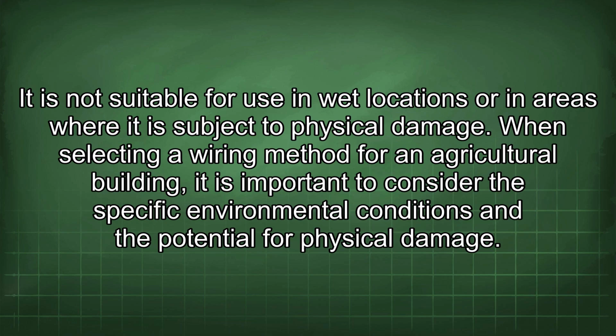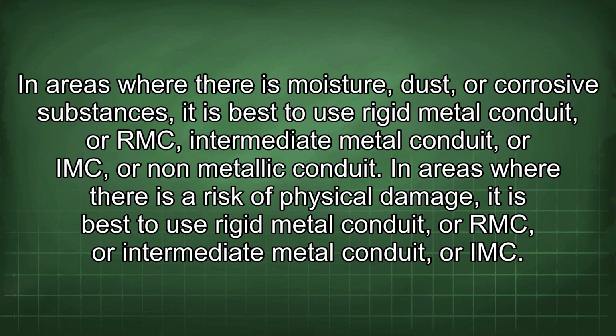When selecting a wiring method for an agricultural building, it is important to consider the specific environmental conditions and the potential for physical damage. In areas where there is moisture, dust, or corrosive substances, it is best to use rigid metal conduit, or RMC, intermediate metal conduit, or IMC, or non-metallic conduit. In areas where there is a risk of physical damage, it is best to use rigid metal conduit, or RMC, or intermediate metal conduit, or IMC.